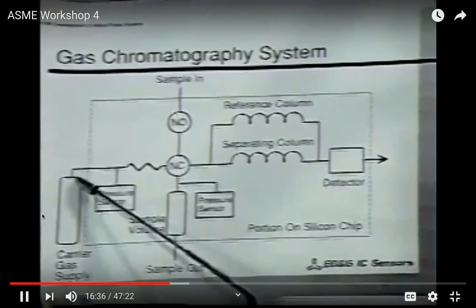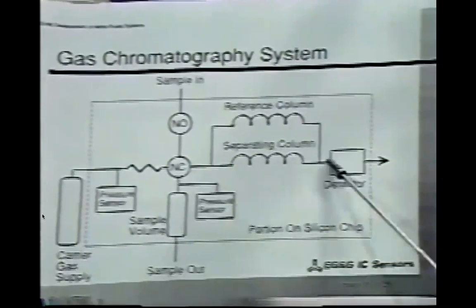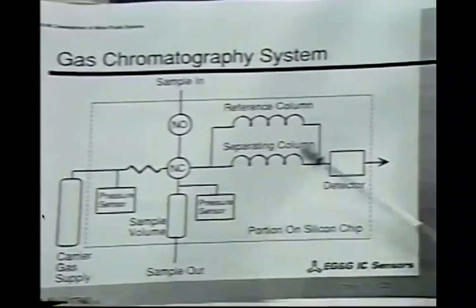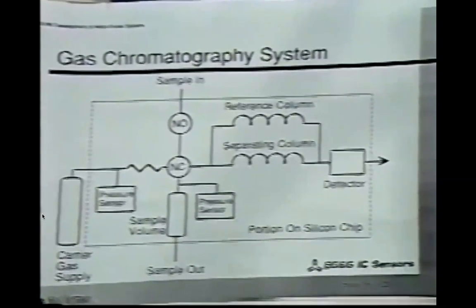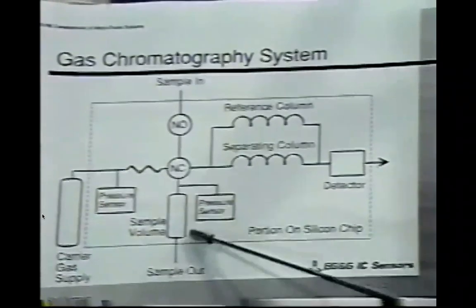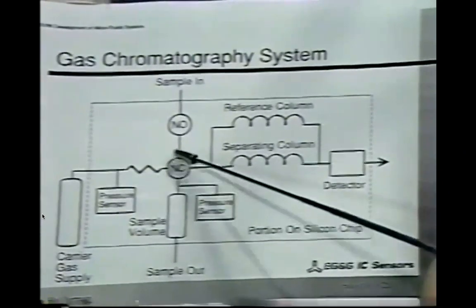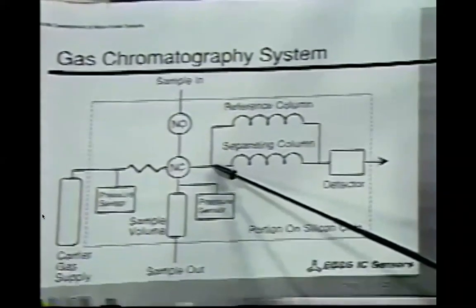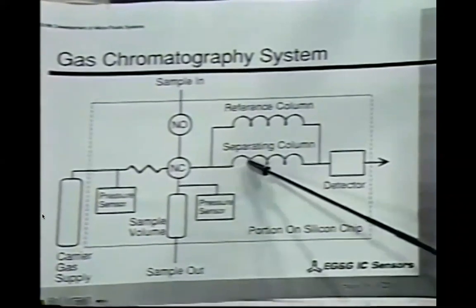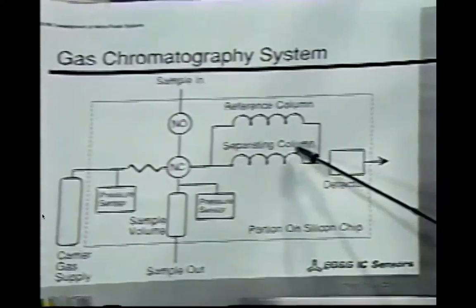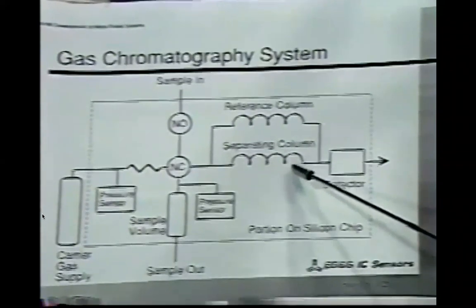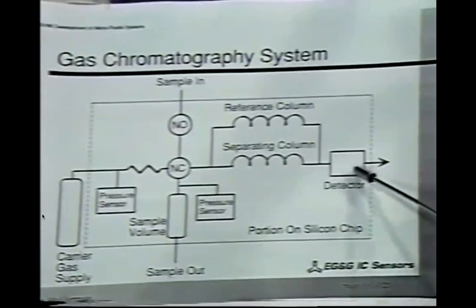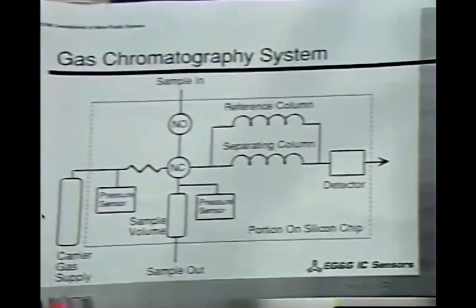An example of such a system, which goes back to our work at Stanford now 20 years ago, is a gas chromatography system. Briefly, a carrier gas, in our case helium, is passed down a very long channel. Part of that is coated with, for example, a hydrocarbon or silicone oil. A sample is injected into the head of this column by an impulsive sample, which starts out at the head of the separating column as a mixture of components. Through a process of diffusion in and out of the column lining as it proceeds down the column, it is physically separated into its constituent components, ethanol from methanol, for example.